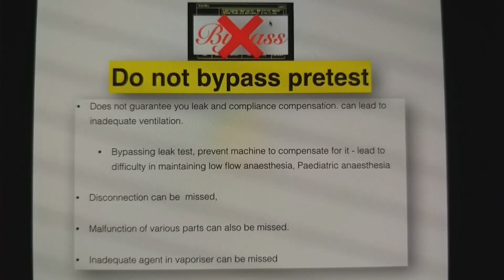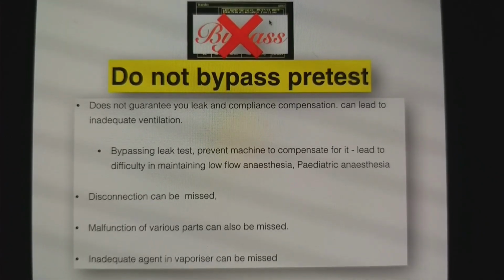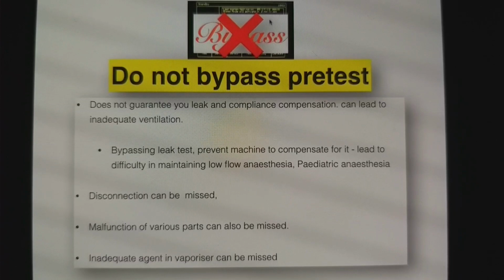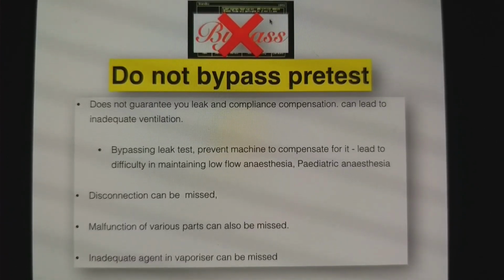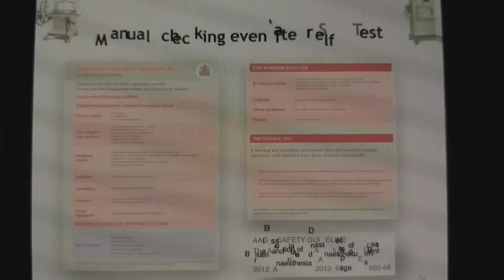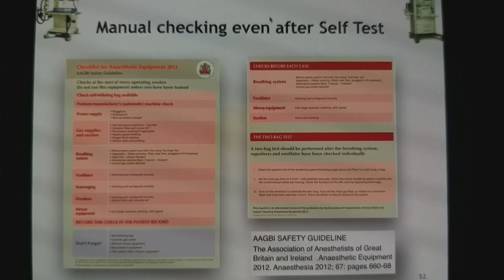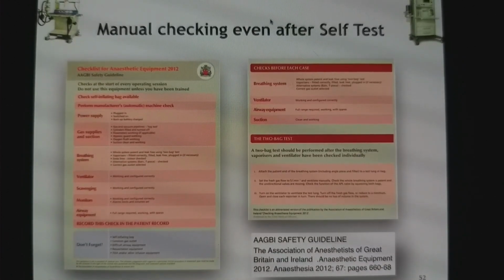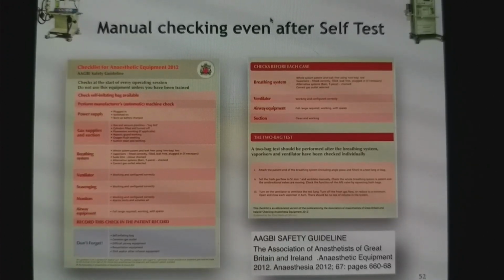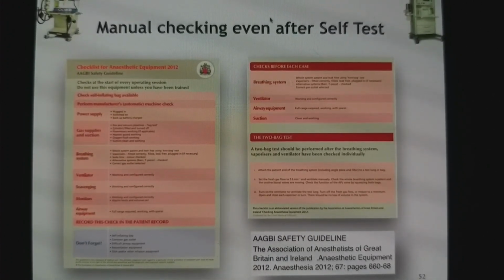In fact, many machines have now come out with a solution where you cannot bypass it more than 8 times. The machine will not allow you to bypass it more than 8 times. Then they will ask you to do the test, and without that, it will not start. In fact, guidelines have come out that after doing the self-test given with the machine, you should again try to do a manual check even after the self-test.